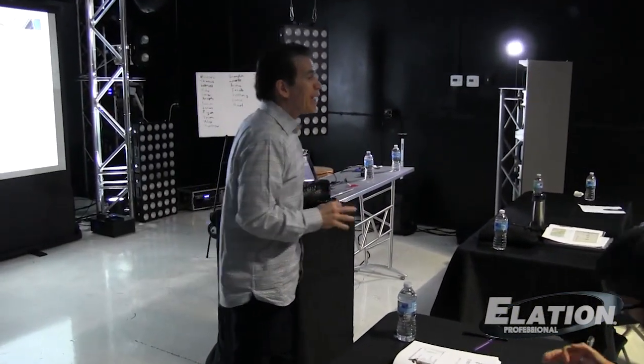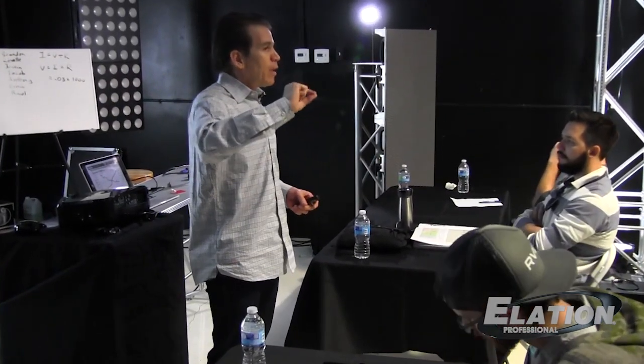Okay, so for those of you who don't know, it's those outlets in your bathroom with the red and black button. Those have protection on them. And the idea is that if somebody's being shocked, it detects what's called leakage current, because when you're being shocked, current's going through your body, it's leaking out of the circuit that it's supposed to be in. And when it detects a tiny bit of leakage, which is 6 milliamps or more, then it will shut itself off. And they will save your life. Those GFCIs are designed to save 99% of the world's population from lethal shock. So who's the 1% that it won't save? Well, very, very small infants and very elderly, or people with health problems. But everybody else, if you're a healthy adult, then a GFCI will save your life.